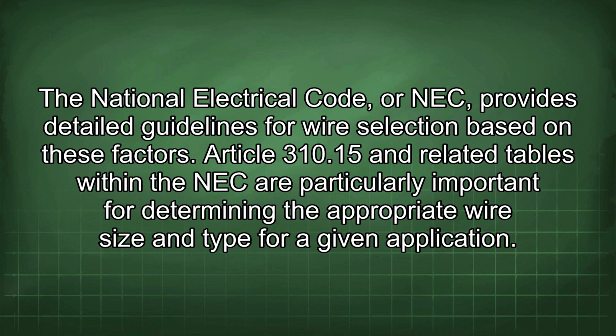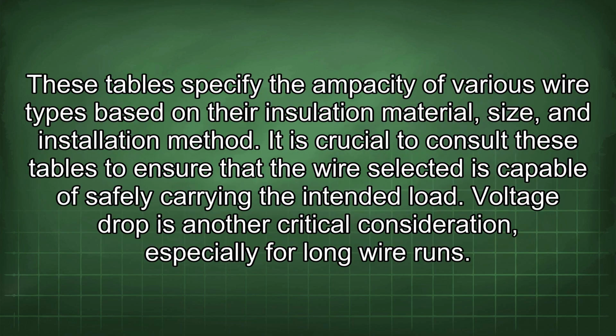Article 310.15 and related tables within the NEC are particularly important for determining the appropriate wire size and type for a given application. These tables specify the ampacity of various wire types based on their insulation material, size, and installation method. It is crucial to consult these tables to ensure that the wire selected is capable of safely carrying the intended load.